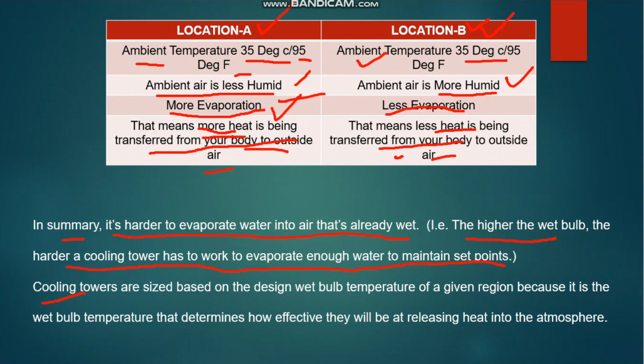So when you go for the selection, cooling towers are sized based on the design wet bulb temperature, not the dry bulb temperature of a given region. So in different regions, the wet bulb temperature is different. We have to consider the wet bulb temperature for the evaporation, because it is the wet bulb temperature that determines how effective they will be at releasing heat into the atmosphere.